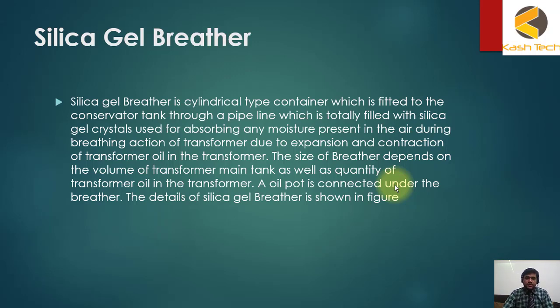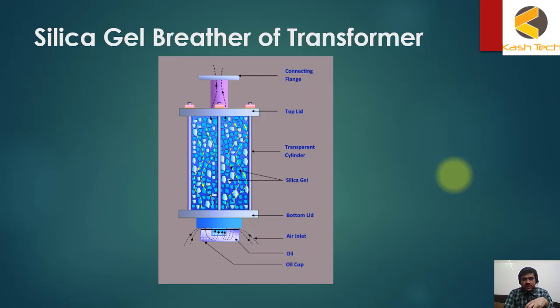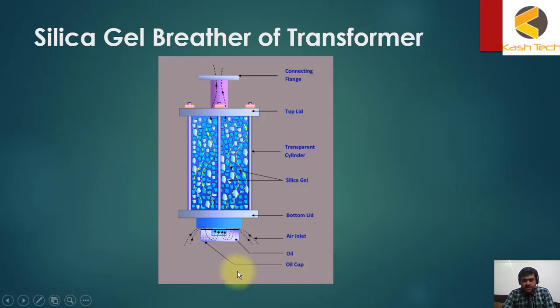So the transformer is literally breathing, and when it does, the oil can absorb moisture. Ideally, this moisture should be trapped. Silica gel has the quality to absorb moisture, so we put a bottle filled with silica gel and when air is going in or out, the silica gel absorbs the moisture so the oil remains in good condition for a longer time.